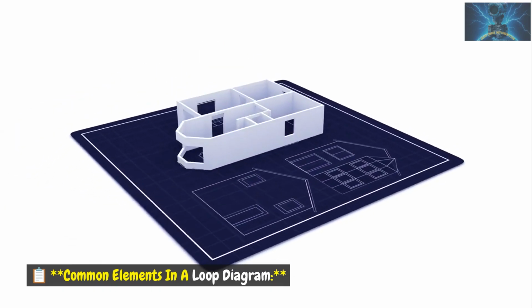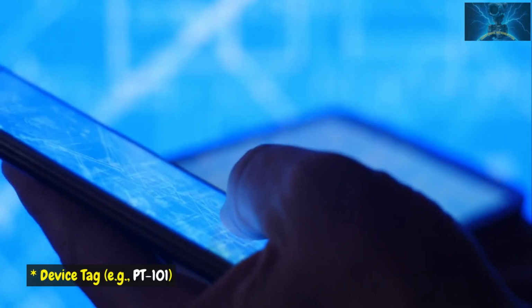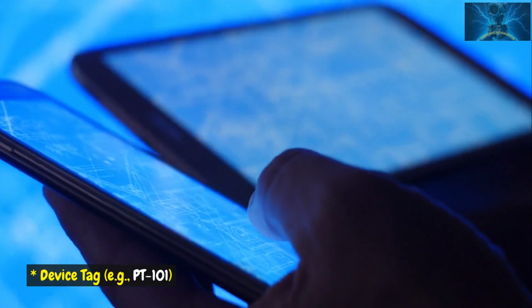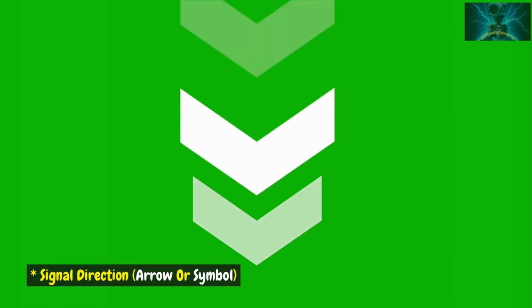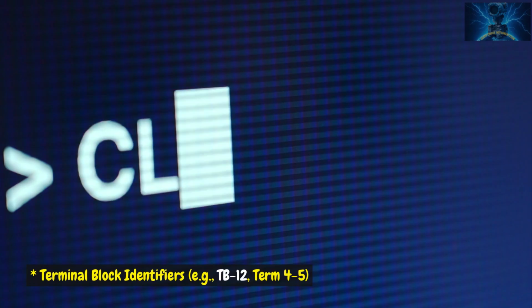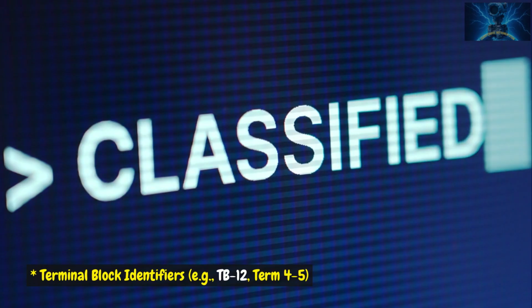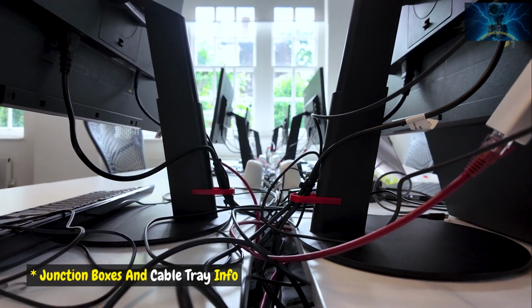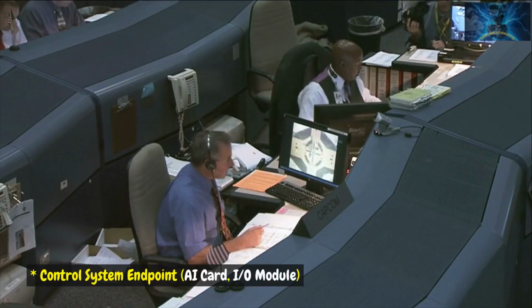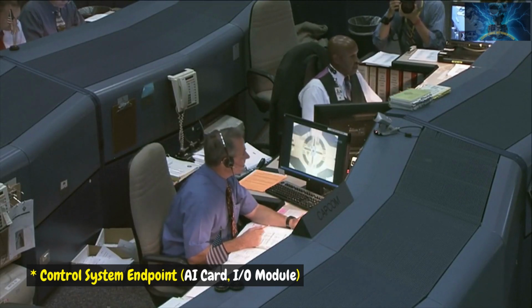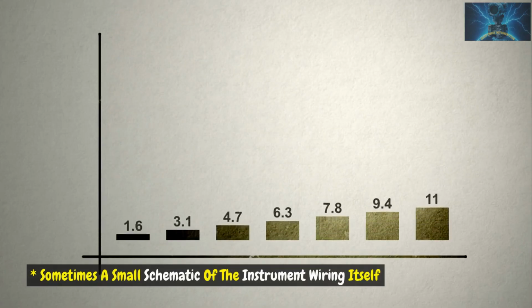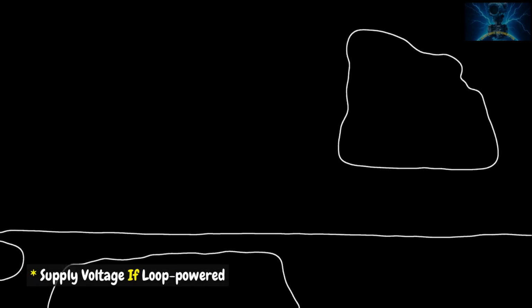Common elements in a loop diagram: device tag, e.g. PT101; signal direction, arrow or symbol; terminal block identifiers, e.g. TB12, term 4-5; junction boxes and cable tray info; control system endpoint, AI card, I/O module. Sometimes a small schematic of the instrument wiring itself. Some loop diagrams even include shielding notes, grounding instructions, and supply voltage if loop powered.